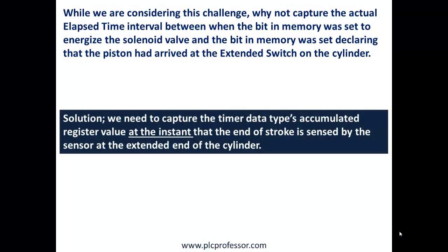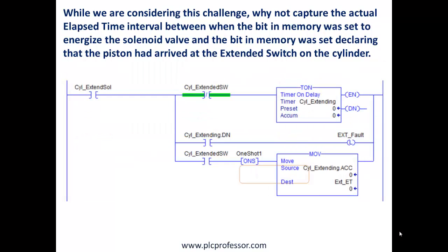If you look closer, you will see a problem with this logic. Now this is the solution. We need to capture the timer's data type's accumulated register value at the instant that the end of stroke is sensed by the sensor at the extended end of the cylinder.